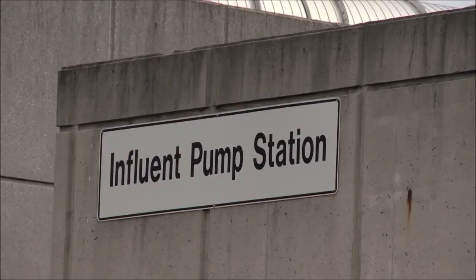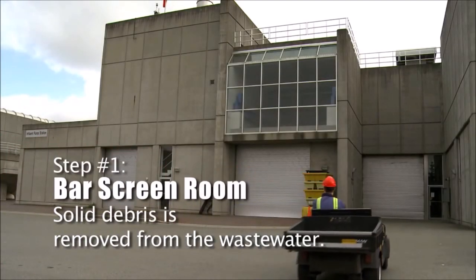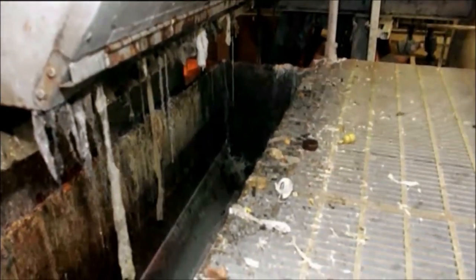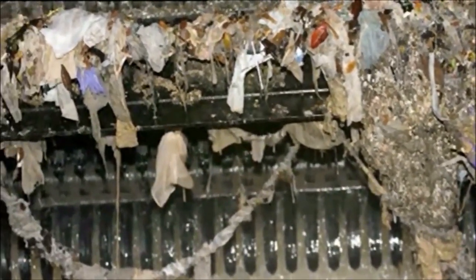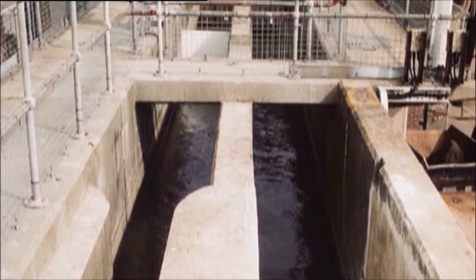The first stage of treatment takes place in the influent pumping station, where solid debris is removed from the wastewater. The incoming sewage passes through screens, where any rags or large debris is removed. Sewage flows through these channels, where road grit and sand is removed.